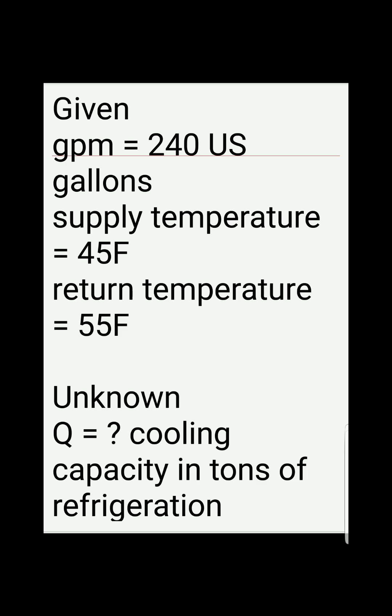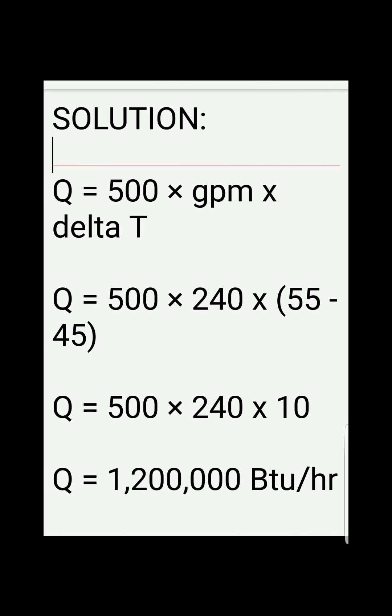The unknown is Q, the cooling capacity in tons of refrigeration. The formula is: Q, or the cooling capacity, is equal to 500 times gallons per minute times delta T.